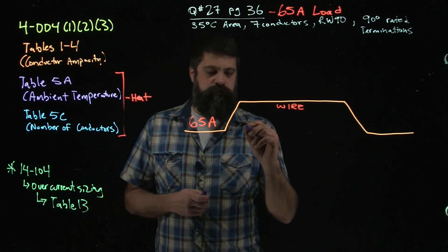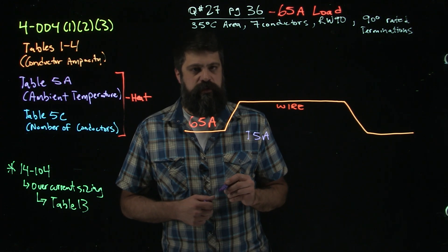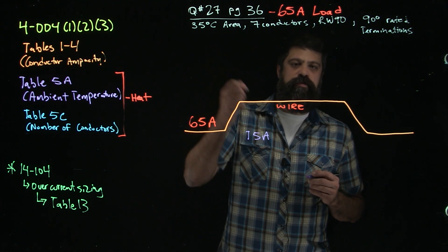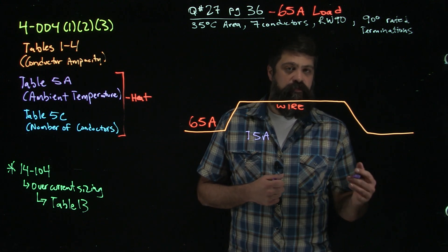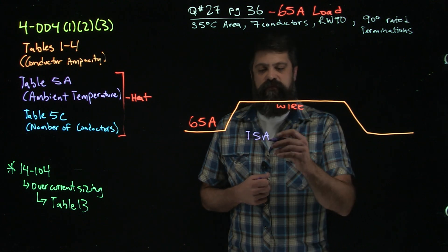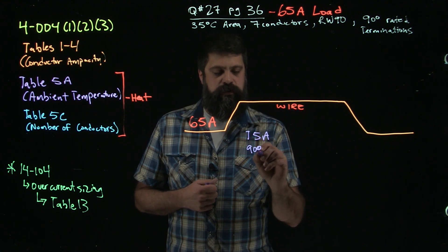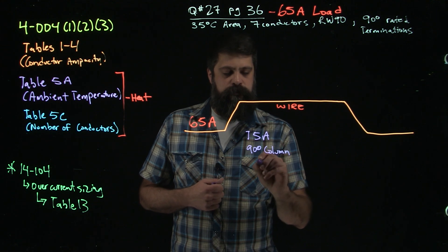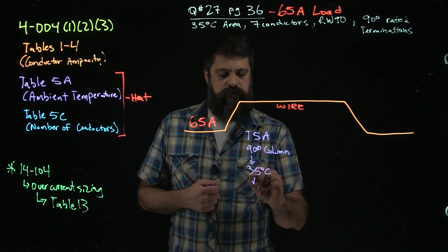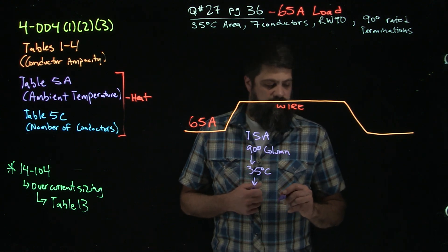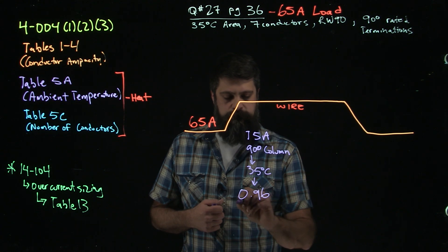So Table 5A is going to give us a number. If I take 35 degrees, I need to make sure that I'm looking in the proper column for what that derating factor is. Table 5A, I'm looking in the 90 degree column at 35 degrees Celsius, which gives me a factor of 0.96.